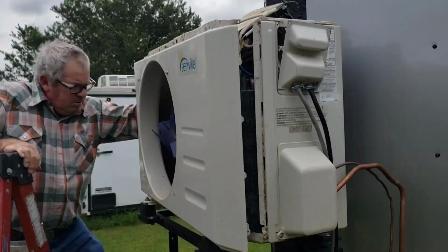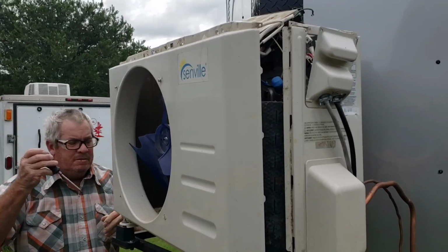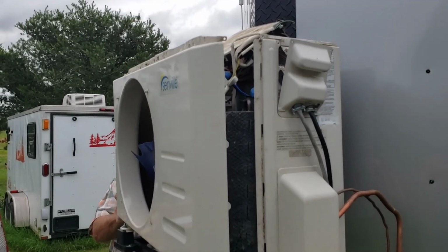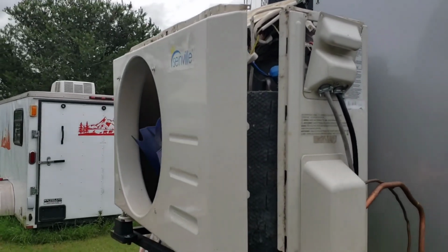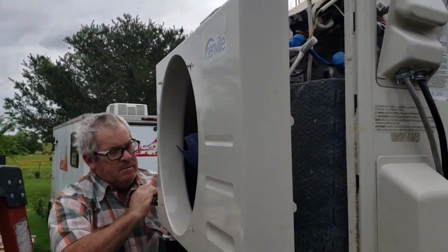But let me tell you, if that capacitor goes out, your central unit will shut itself down. We're in Oklahoma right now, where we actually had our 3 hottest days this past week when ours went down. So luckily we got it fixed pretty quick. Again, that has to recharge also, so it takes a little while for it to come back on too. So that's where we're at. And the capacitor, I don't know if you guys can see it. It's that round tube thing, and I only know that because I'm the one that saw it on our big unit out there.